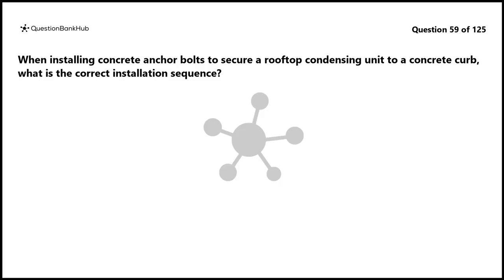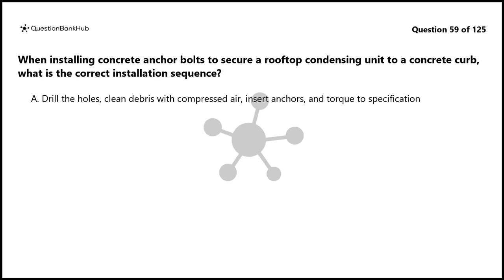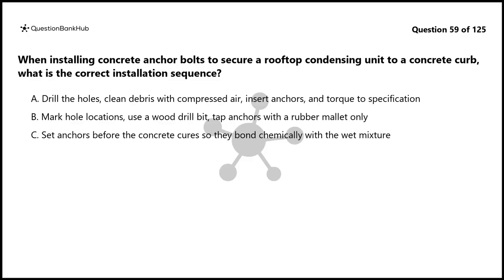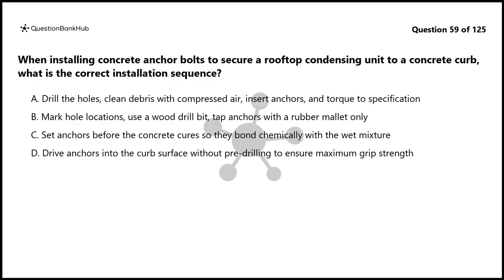Question 59. When installing concrete anchor bolts to secure a rooftop condensing unit to a concrete curb, what is the correct installation sequence? A. Drill the holes, clean debris with compressed air, insert anchors, and torque to specification. B. Mark hole locations, use a wood drill bit, tap anchors with a rubber mallet only. C. Set anchors before the concrete cures so they bond chemically with the wet mixture. D. Drive anchors into the curb surface without pre-drilling to ensure maximum grip strength.